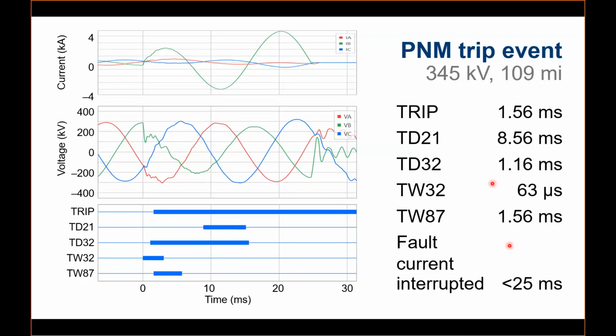And the total fault clearance time is just the breaker time, because 1.56 milliseconds is negligible as compared to the breaker time. So if you have a 1 cycle or 1.5 cycle breaker, you can just consider the breaker time for the total fault clearance. So you will have a much faster fault clearance. It means it is adding to the system stability. The faster you clear the fault, the more stability you add to the system, and you will have more power transmission capability, and the system will not go into unwanted swings or disturbances.